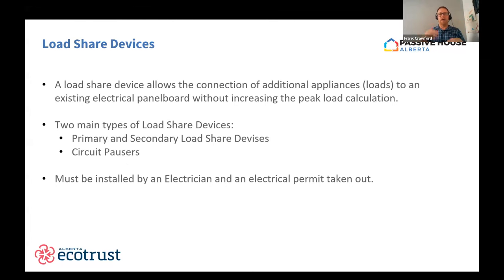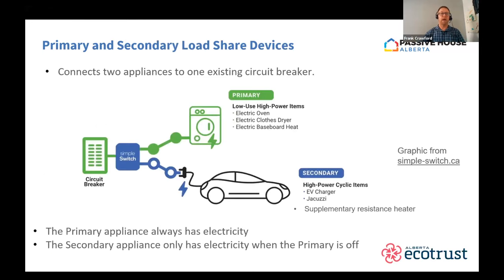There are two main types. The names vary from location to location, but what I've seen most often is a primary and secondary load share device, or a circuit pauser. These pieces of equipment are electrical equipment, so they must be installed by an electrician, and you do need to pull an electric permit to install these. Briefly, with the primary and secondary type of load share device, as the name implies, you have one breaker, use that breaker to go to the primary and secondary device, and then you have two appliances. One is the primary, it always has power. The second is the secondary. It has power only when the primary is off. So this is good for when you have two appliances that have similar loads, but run at different times.